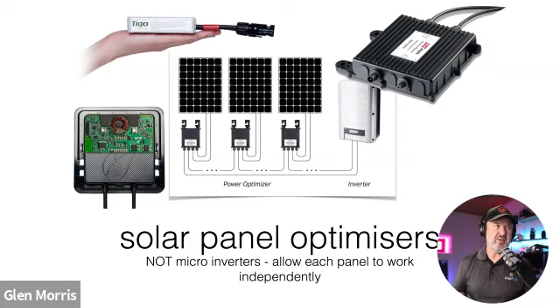And it also can add safety, because in a DC string, certainly in 3-phase, you're in 800 or 900 volts, so you've got very high DC voltages on the roof of a commercial building. But when you have optimizers, the highest DC voltage that's not managed safely is one panel. The string, even though it might still be in hundreds of volts, is dependent on those optimizers sensing that they're safe to operate. So for instance, if there's a fault, the whole thing shuts down automatically and you've got no high DC voltages anywhere. So safety is a big plus.